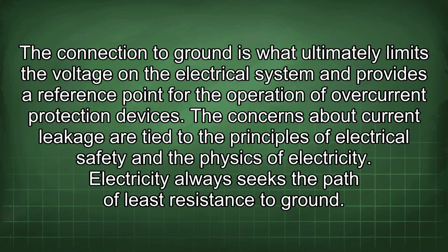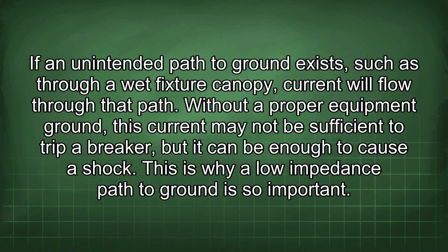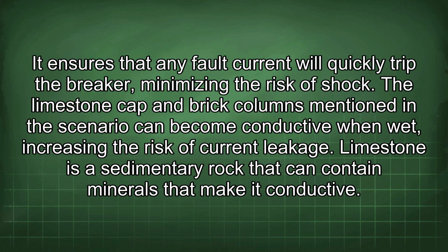The concerns about current leakage are tied to the principles of electrical safety and the physics of electricity. Electricity always seeks the path of least resistance to ground. If an unintended path to ground exists, such as through a wet fixture canopy, current will flow through that path. Without a proper equipment ground, this current may not be sufficient to trip a breaker, but it can be enough to cause a shock. This is why a low-impedance path to ground is so important. It ensures that any fault current will quickly trip the breaker, minimizing the risk of shock.